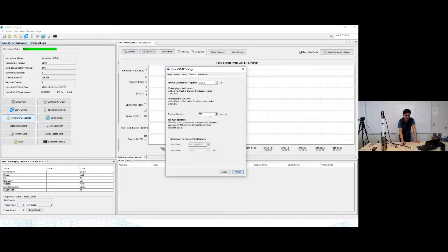Now, if you're doing autonomous sampling, you also have a pre-flush duration. This is meant to just get any bubbles out of the plumbing and then really get new, fresh water into your instruments before it starts sampling autonomously. By default, this is 300 seconds. When you start, say, a delayed sampling autonomously, your HydroCAT EP is going to meet the time when it's programmed to start sampling, flush for 300 seconds, and then start the sampling routine. You can change this more or less depending on your application, and you can also schedule that pre-flush based on when you plan to deploy your instruments.